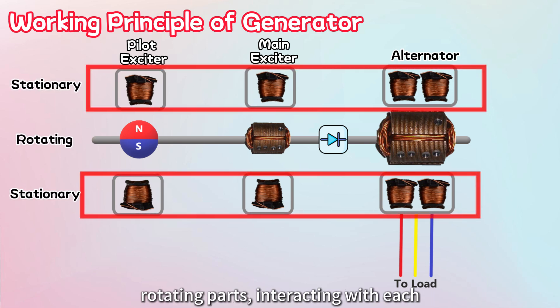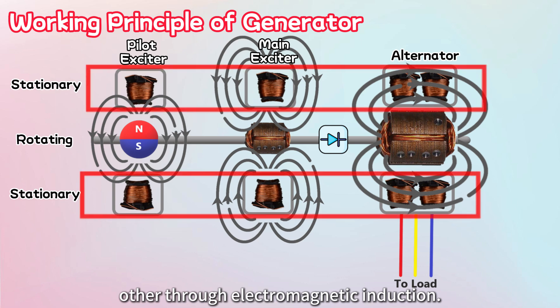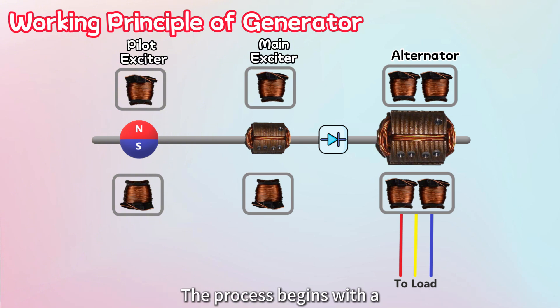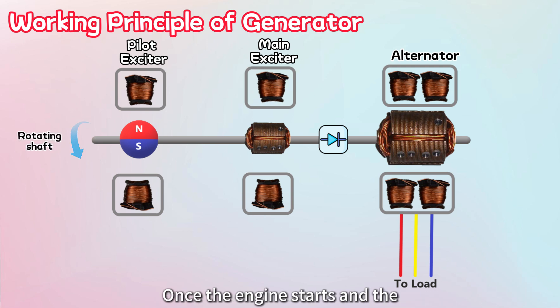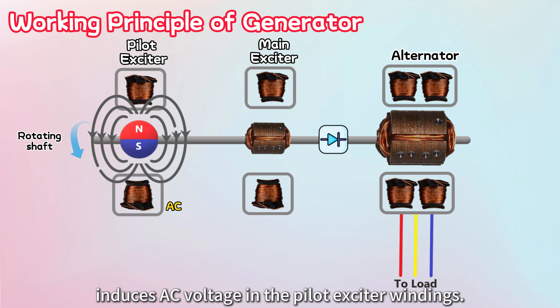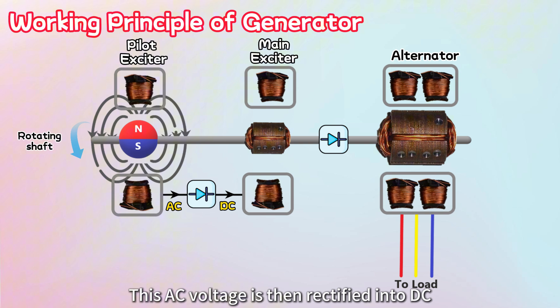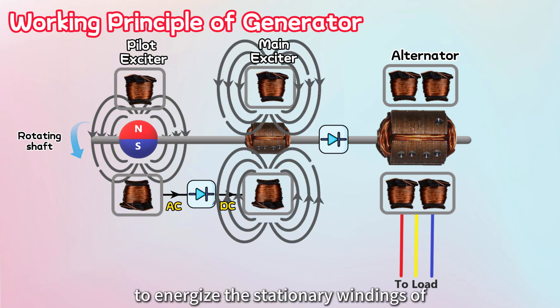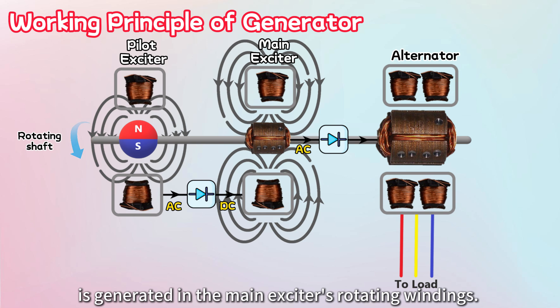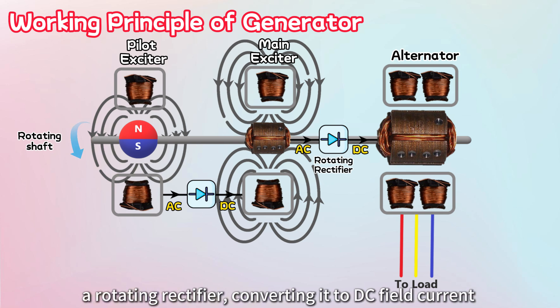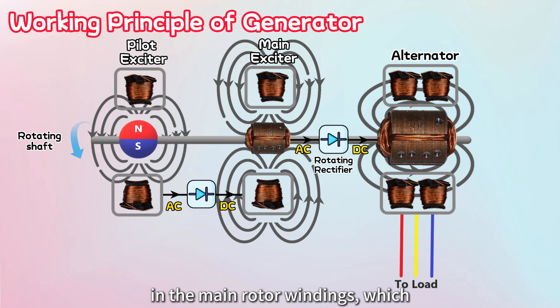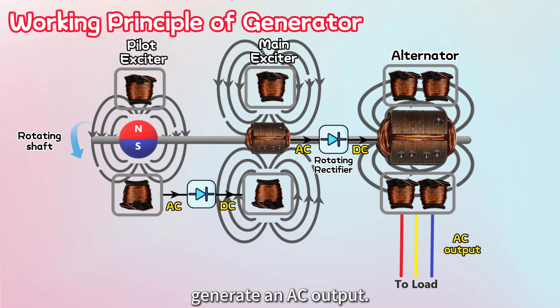These exciters contain both stationary and rotating parts interacting through electromagnetic induction. The process begins with a pilot exciter that uses a permanent magnet. Once the engine starts and the rotor begins to rotate, the rotating magnetic field from the permanent magnet induces AC voltage in the pilot exciter windings. This AC voltage is then rectified into DC to energize the stationary windings of the main exciter. Through electromagnetic induction, AC voltage is generated in the main exciter's rotating windings. This AC output is then rectified using a rotating rectifier, converting it to DC field current flowing in the main rotor windings. This setup produces a rotating magnetic field in the main rotor windings, which cuts across the main stator windings to generate an AC output.